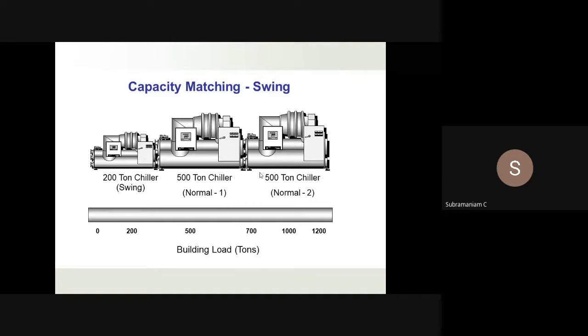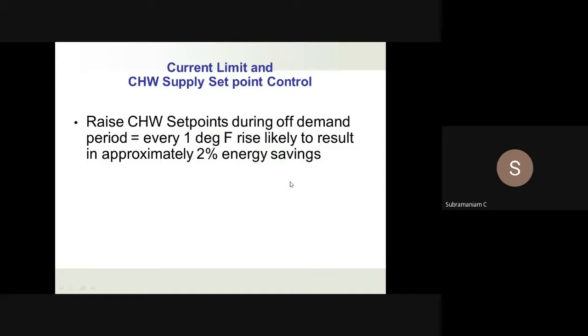So we can have different size chillers. If your capacity is varying from 200 to 1200 ton for a building, it's not that we have to put three chillers of 400 ton. We can put two of 500 and one of 200, and then operate the chillers based on the load requirement.